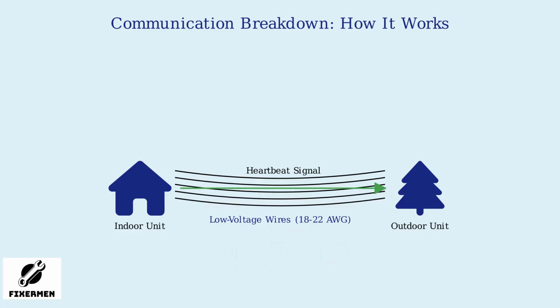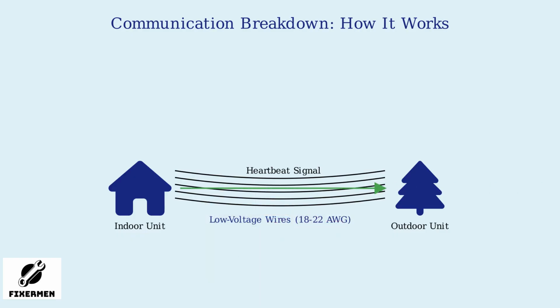The indoor board sends regular heartbeat signals to the outdoor unit. These signals act like digital check-ins, confirming that both units are communicating properly. Think of it as a digital check-in system between the two units, similar to how communication processes work in event requests and alerts. If these heartbeat signals are interrupted or not received by the outdoor unit within a set time, the F07 error is triggered. This could be due to wiring issues, power problems, or other faults in the communication system.